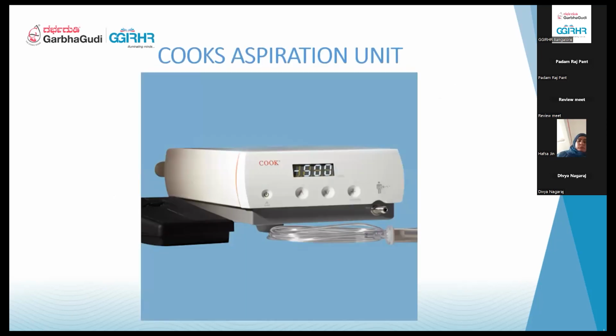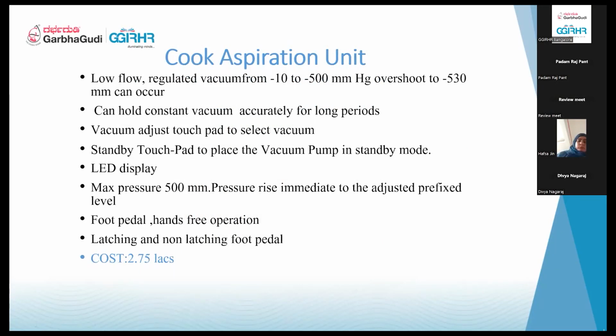110 to 120. This is the aspiration unit or the suction unit, where we preset the suction pressure that we want. Through this, the tubing is connected to the cork, which fits onto the test tube. The Cook aspiration unit has a low flow regulated vacuum, which can create a vacuum somewhere between 10 to 500. But what we require is around 100 to 120. The advantage of this suction apparatus is that it maintains a constant vacuum accurately for long periods. The vacuum adjusts with a touchpad to select the vacuum. A standby touchpad is available. It has an LED display. Maximum pressure is 500, which is again not required for us.